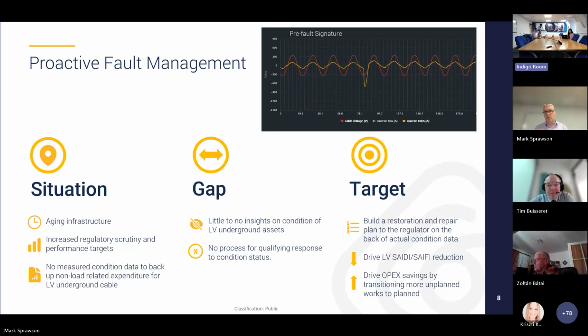However, something happened to cause that spike. Grid edge intelligence can run clever algorithms on the device to help you identify how worried you should be about that spike—whether it's because a fault is developing and breakdown is happening in that cable joint or in that low voltage cable.